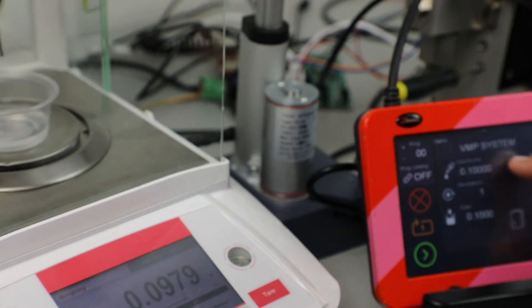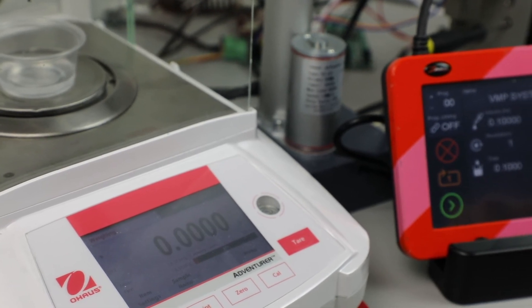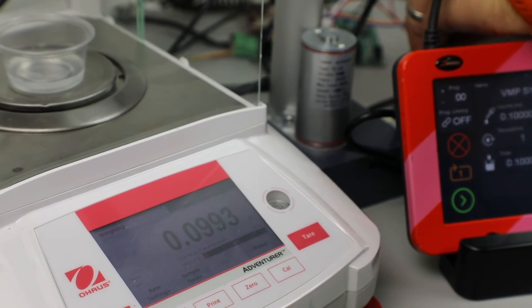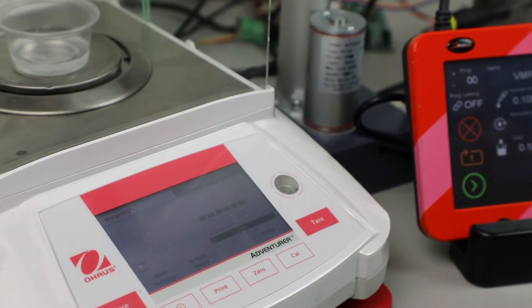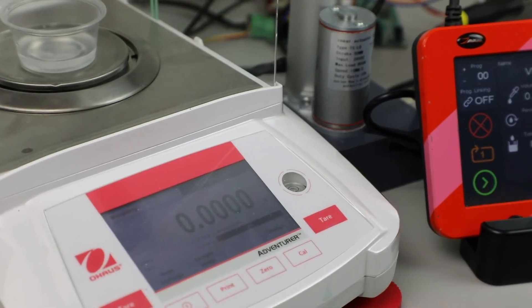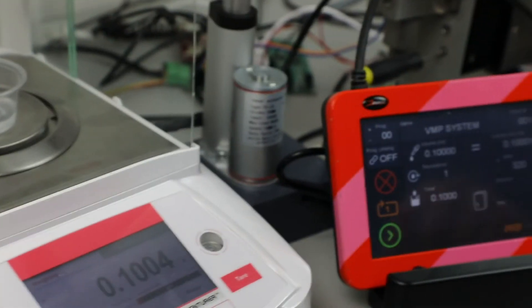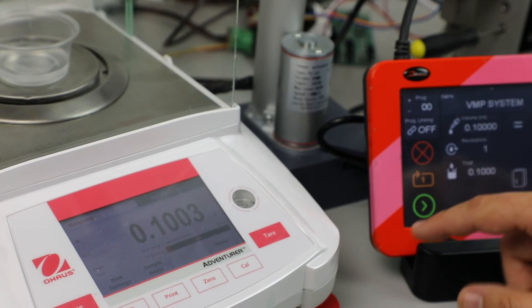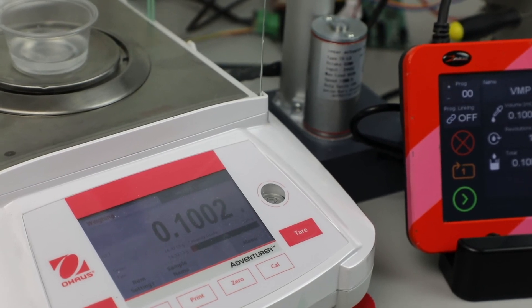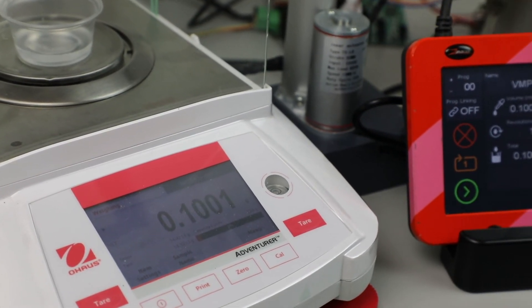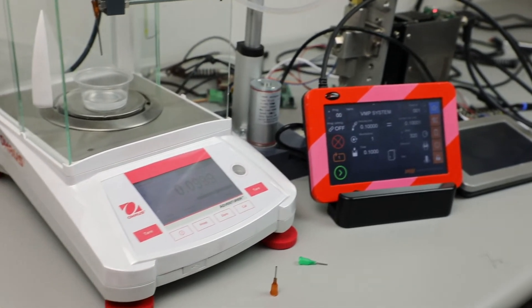Let me double check that. Now I'll make a small adjustment the other way. Tare our scale. I'm getting closer. A few back and forth with this. This is normally done at the factory with a standardized setup, tubing included and tip. But for the purpose of this video, I'm going to call it probably close enough. Let's see where we, if we get right at the target. So here we are right at the target. Again, that was a mechanical adjustment showing that only because most of you are not pumping water. You're going to be pumping something that has a different specific gravity.